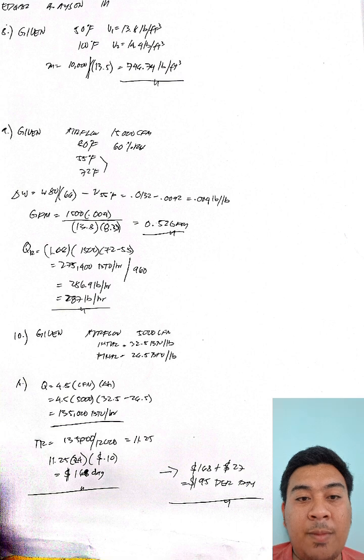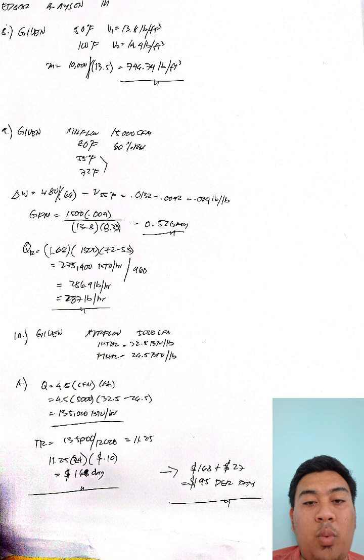For number 10, a gym is maintained at 75 degree Fahrenheit with 60% relative humidity, with an enthalpy of 32.5 BTU per pound. The owner wants to lower the relative humidity to 40%, at 75 degree Fahrenheit, where the enthalpy is 26.5 BTU per pound. A. Calculate the total heat removal required for 5,000 CFM using the formula 4.5 times CFM times delta enthalpy, or delta H. Then B, if achieved by cooling to dew point and reheating, calculate the total energy cost per day with cooling at 0.10 per ton hour and steam at 0.05 per pound.